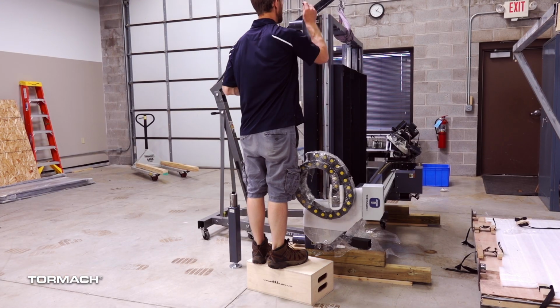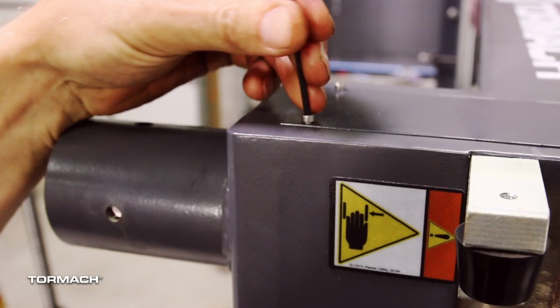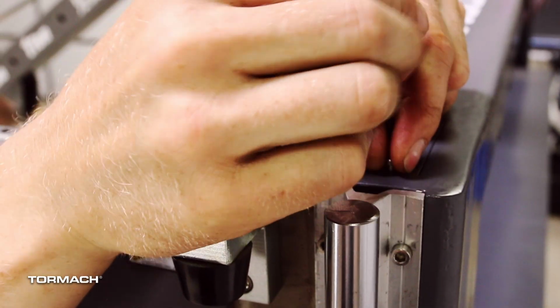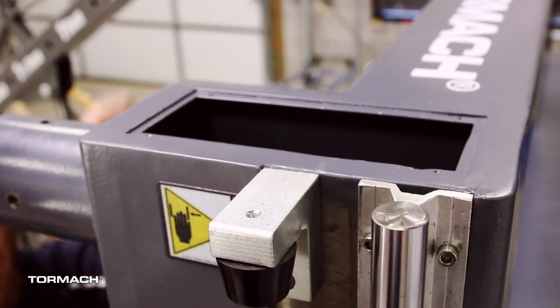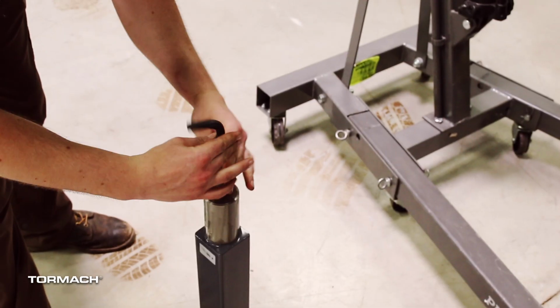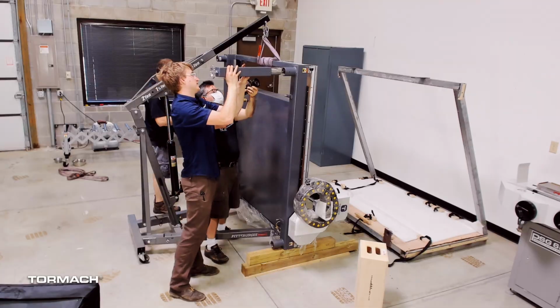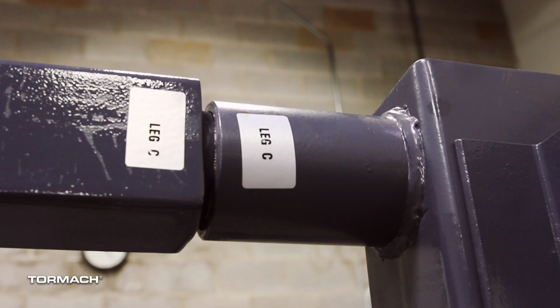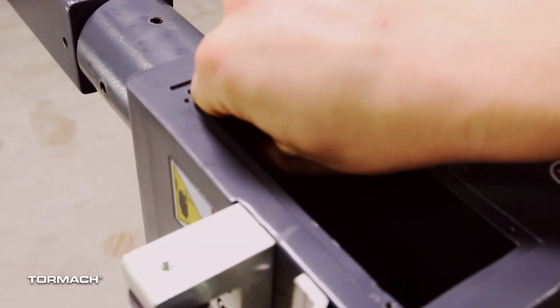We're going to remove the cover plates from the end of the machine to access the leg mounting locations. We're going to need a 2.5mm Allen wrench for this. We can remove the shipping bolts from the top of each leg. The location at which we install the legs is important. You'll find labels on each leg and on the table. We'll need to match these up and get the top 2 legs installed.